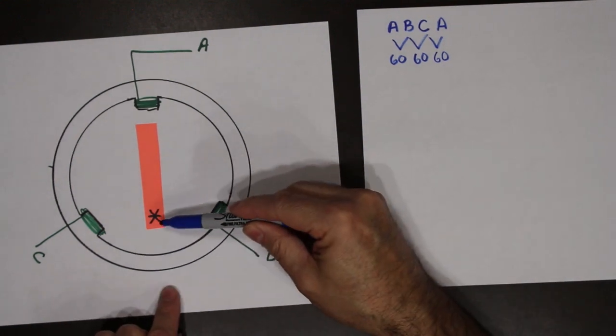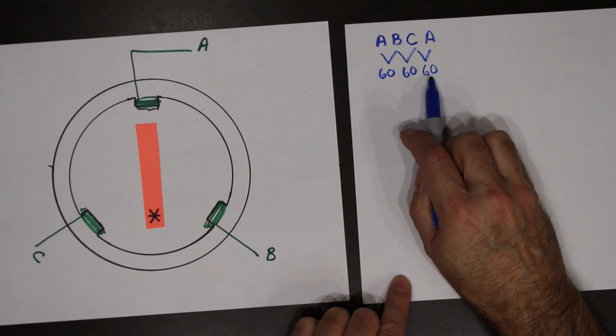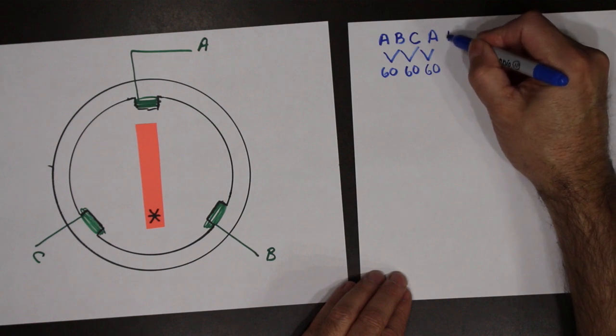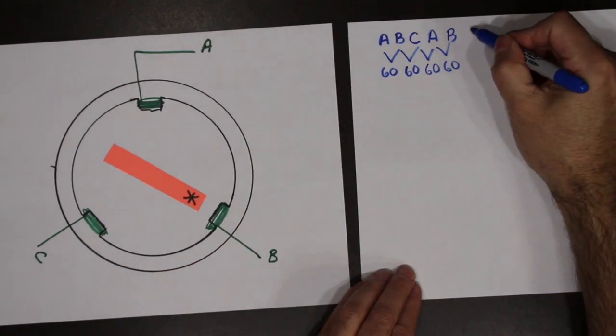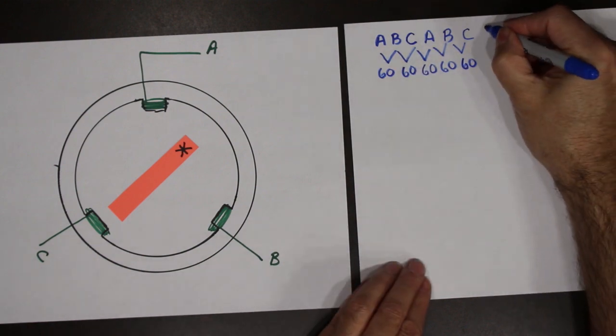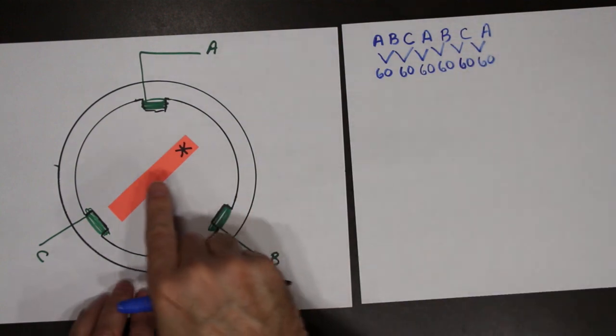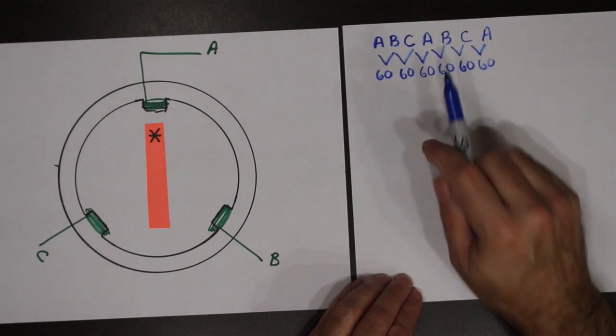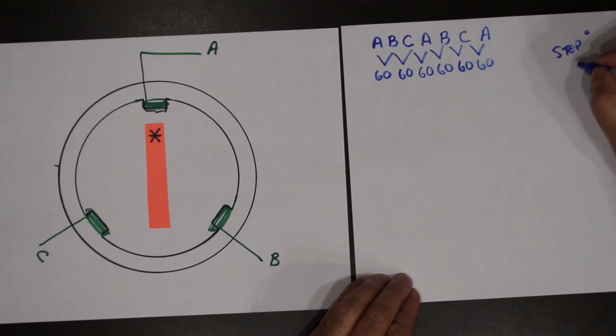Continuing: energize A, it attracts the closest part — another 60 degree step. I started with the star up top and now it's at the bottom; I have rotated 60, 120, 180 degrees in three steps. Continuing to B — that's another 60 degrees — then C, another 60 degree step, then back to A, another 60 degree step. So every step I am moving 60 degrees. My step angle for this example is 60 degrees.